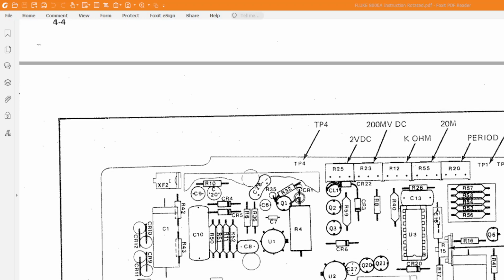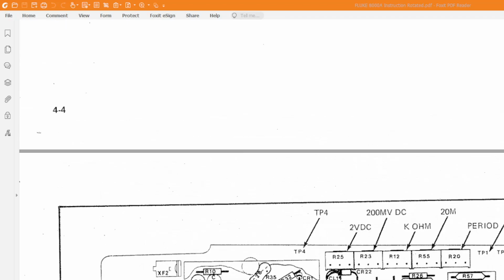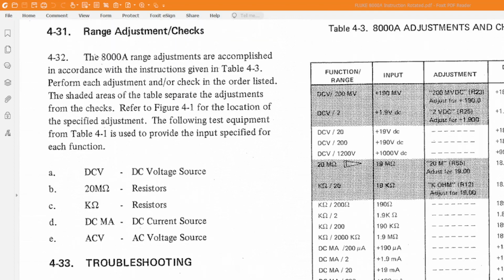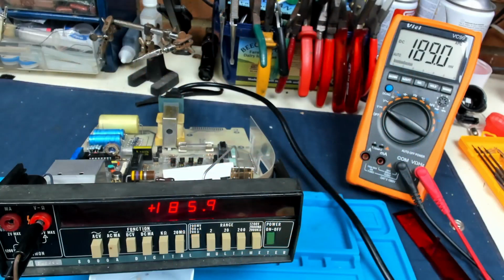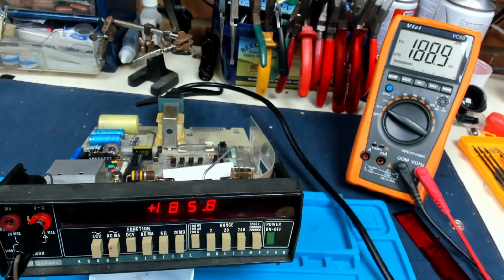So the one we'll be interested in is the second one along. It says 200 millivolts DC. So if we come back up to here on the table, it says DC 200 millivolts, input 190 millivolts. And if we go back to the bench, we can see that I've reduced my power supply. It's been running for a little while to get it nice and warm. 189.9 I can get on my Vicky meter. I'll just keep tapping that control slightly. Obviously if you're going to do any serious calibration, really what you need to do is turn your power supply on, your voltage source, whatever, and let it get up to good temperature, because as you can see at such low voltages that it's varying slightly.